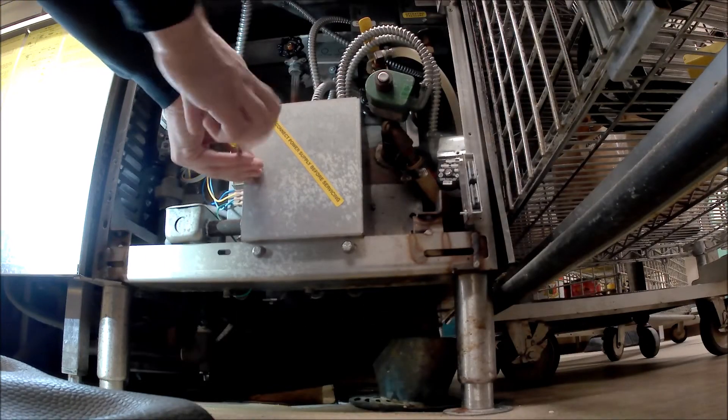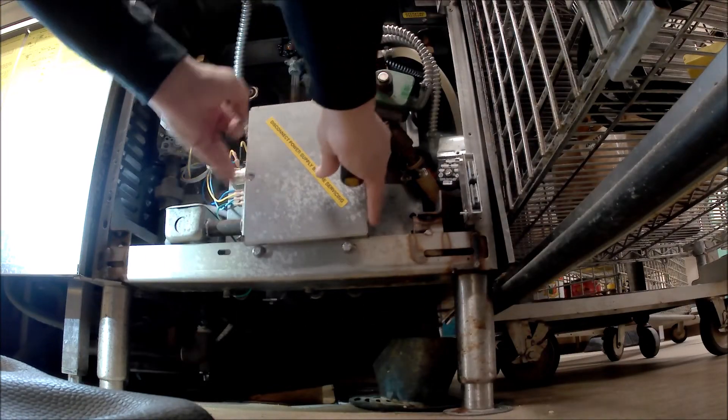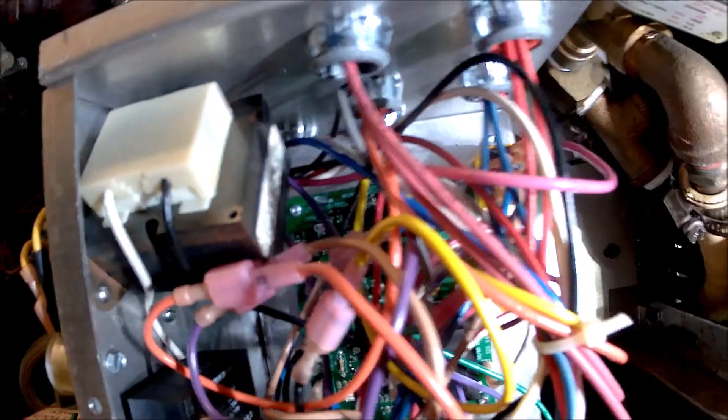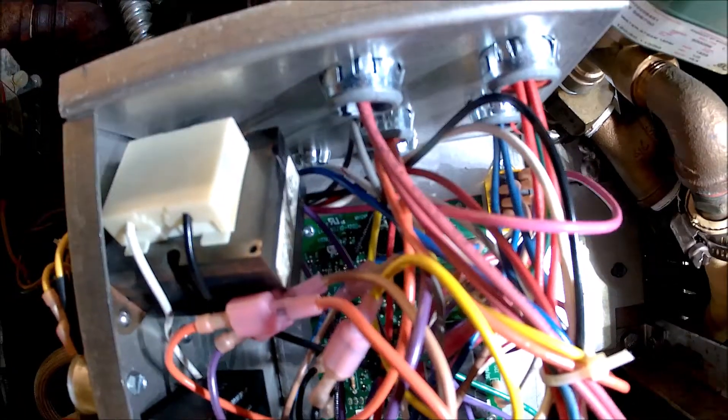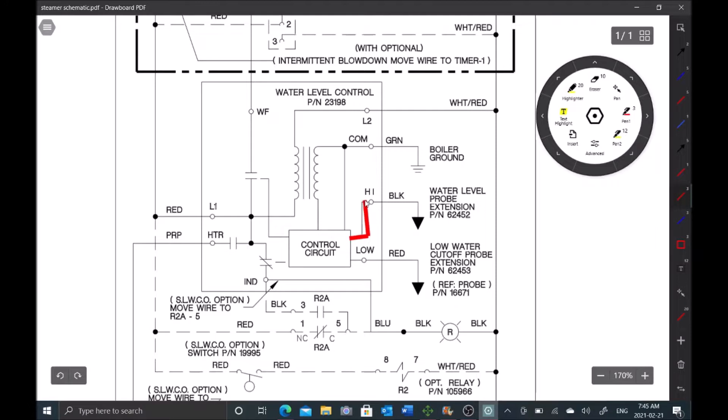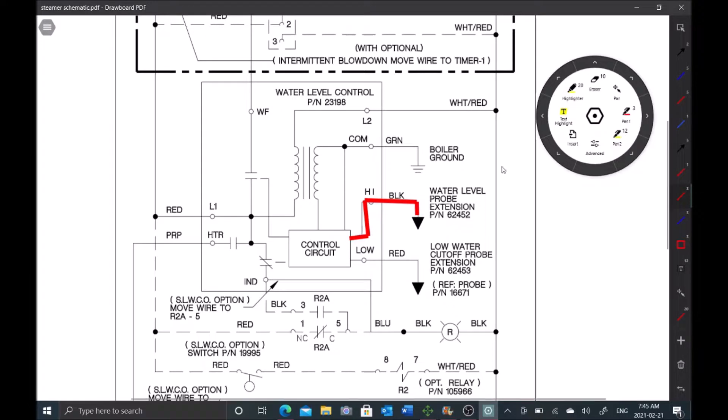Let's go ahead and test this low water probe. It can be tested very easily. That red light is telling me it is sensing water. I'm going to pull the wire just to show you - pull the wire, the red light comes off. So we know our high water level probe is good because our solenoid stopped filling.